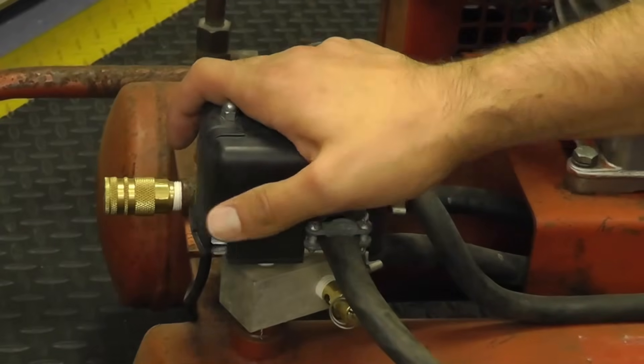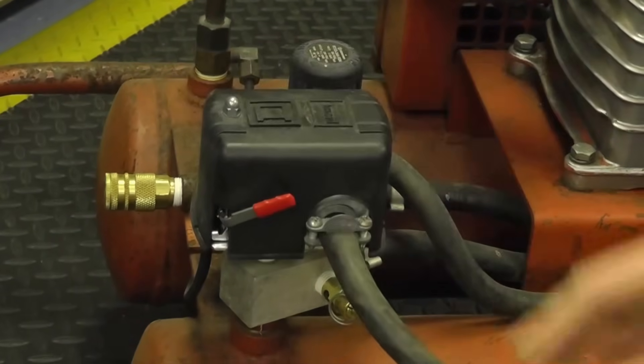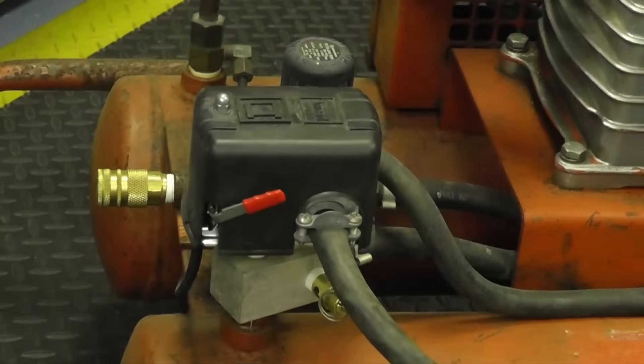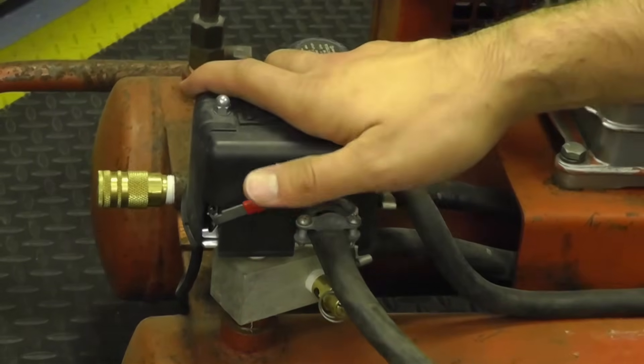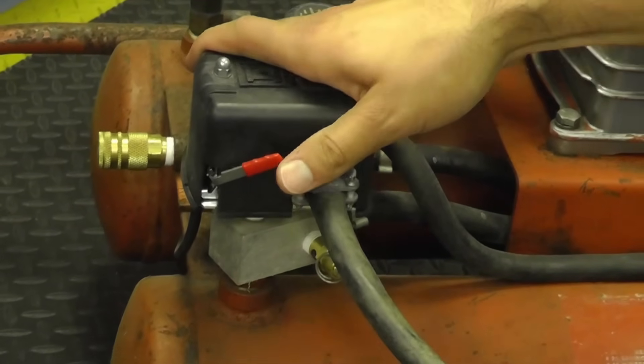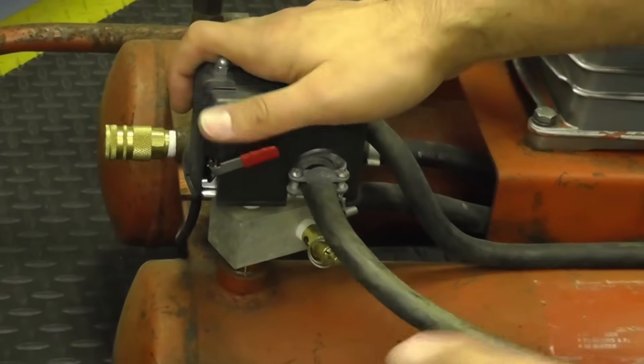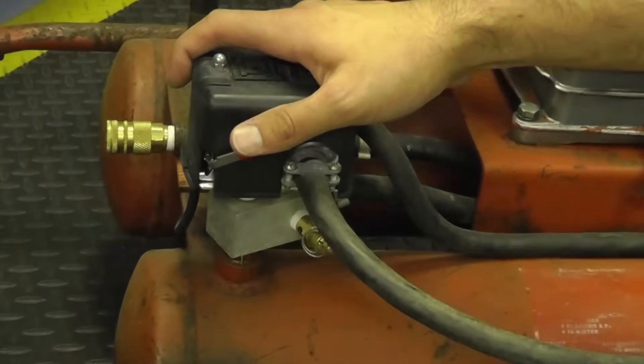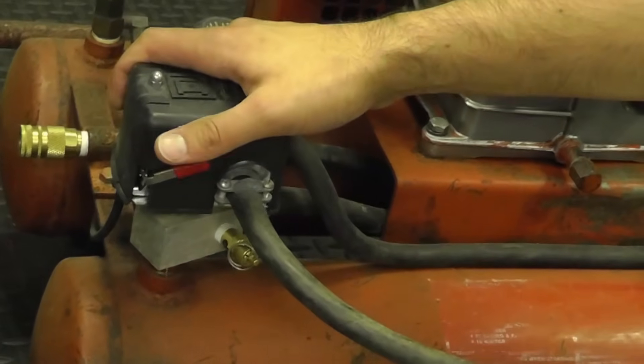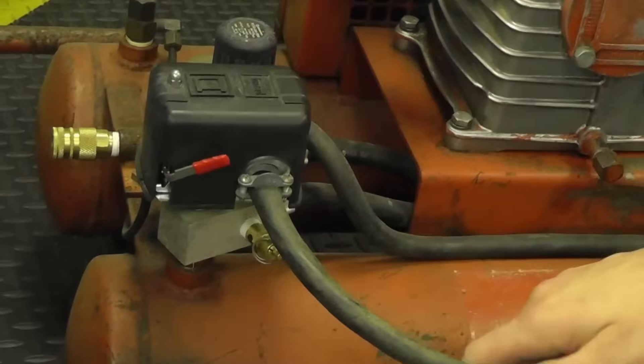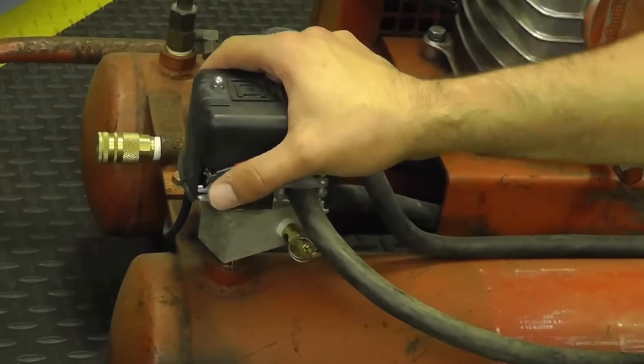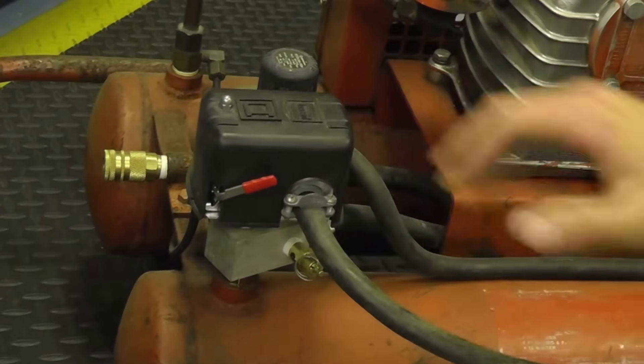This is 90 PSI cut on pressure and 125 PSI cut off, and that is pre-controlled and preset at the factory. So you don't have to turn it off and on manually. Your pressure switch is wired, it wires to your motor. Your motor and power cord wired to your pressure switch. This is a pretty popular component to replace. Sometimes your wires get fried, you have too many amps running through your switch, so it'll fry your contacts. So that's a very popular part we sell. Your pressure switch is really one of the main components, the brains of the compressor.